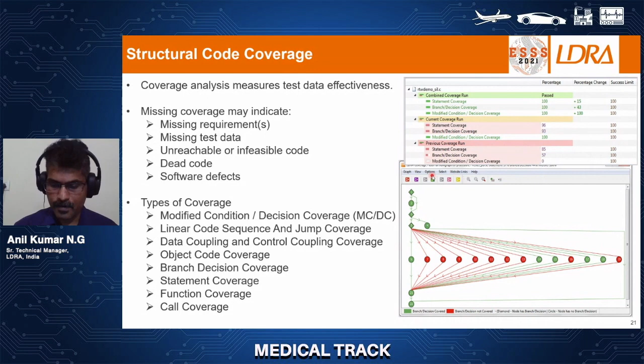And what are the different tests you can perform which can yield structural coverage analysis? One among them is unit testing, and there is a clear-cut indication as far as 62304 is concerned. You need to do a detailed unit test, wherein you refer to the low-level requirement or your design document. Based on that, you start designing your test cases, and those test cases then need to be exercised on the code that has been developed, either on the target platform or on a simulated platform. You can also do it on a host machine to an extent, but it is recommended that all these tests be run on the exact target hardware that is going to be launched.